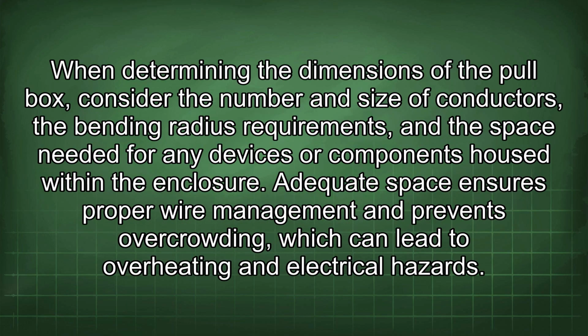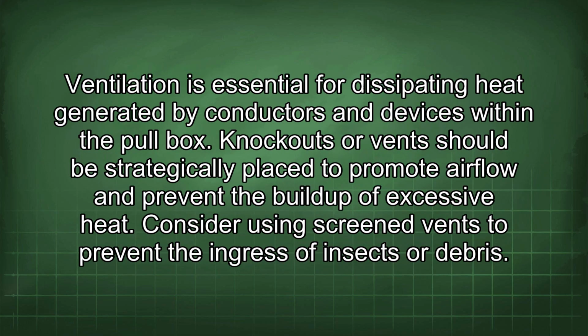When determining the dimensions of the pull box, consider the number and size of conductors, the bending radius requirements, and the space needed for any devices or components housed within the enclosure. Adequate space ensures proper wire management and prevents overcrowding, which can lead to overheating and electrical hazards. Ventilation is essential for dissipating heat generated by conductors and devices within the pull box. Knockouts or vents should be strategically placed to promote airflow and prevent the buildup of excessive heat. Consider using screen vents to prevent the ingress of insects or debris.